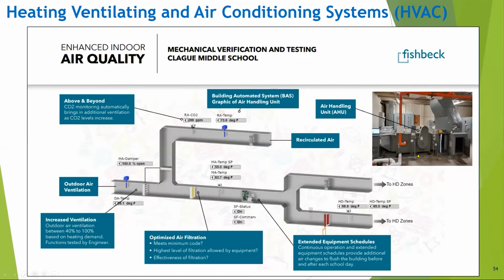Another type, this is more of an air handling unit that serves multiple rooms. It's a very similar graphic. You have your outside air ventilation, your dampers, your recirculated air passes over a filtration medium, is pulled through by a fan, and then it goes out in ductwork to various different spaces. Again, they're looking at this. How much outside air can we bring in? How good of a filter can we have? And is the filter properly installed and effective? And then maximizing our ability through the building automation system to control these systems to make sure we're getting the best ventilation possible with the equipment that we have.